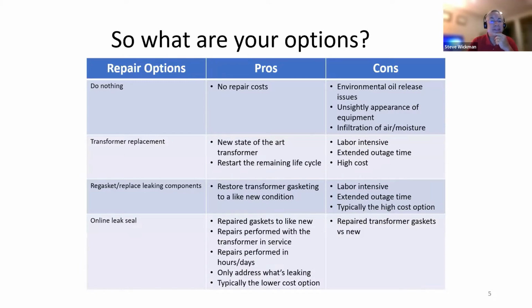So what are your different options? Very first option, do nothing. The pro there is there's no repair cost, but on the con side, let me highlight the last bullet point there, the infiltration of air and moisture. A shout out to Drew in his presentation: I think in your second slide you said that one of the greatest causes of moisture getting into transformers is leaks. So lo and behold, we can offer a technique for you to contain and stop those leaks, to minimize not only your oil release issues, environmental issues, and unsightly appearance, but also infiltration of air and moisture.